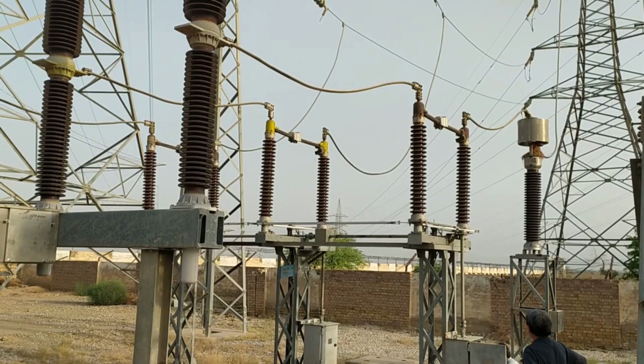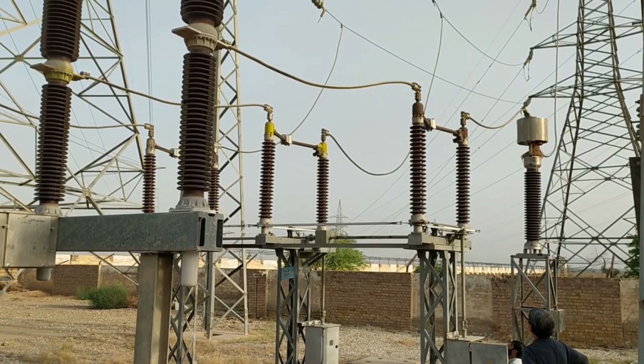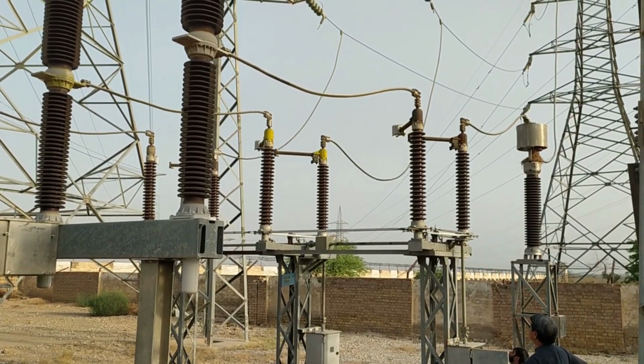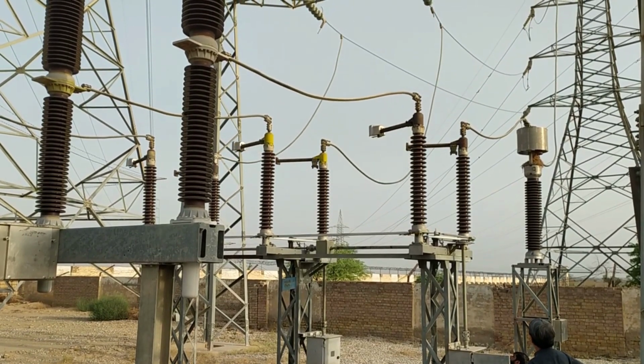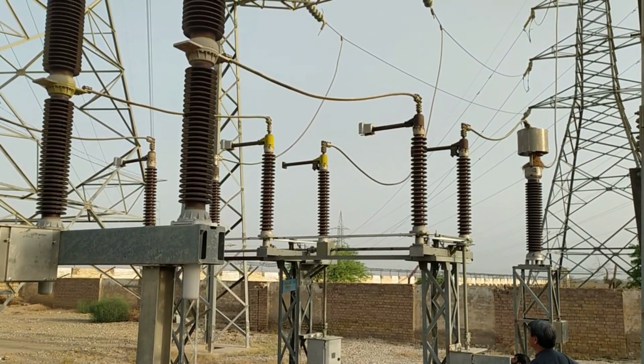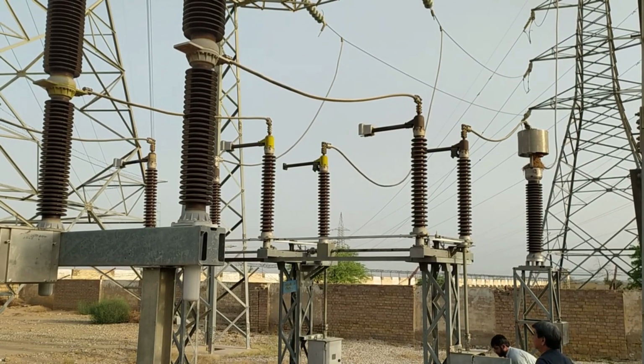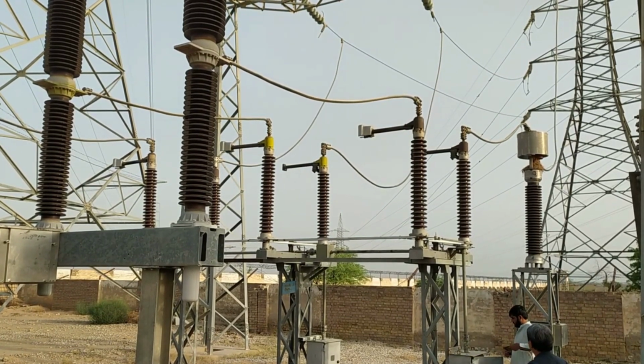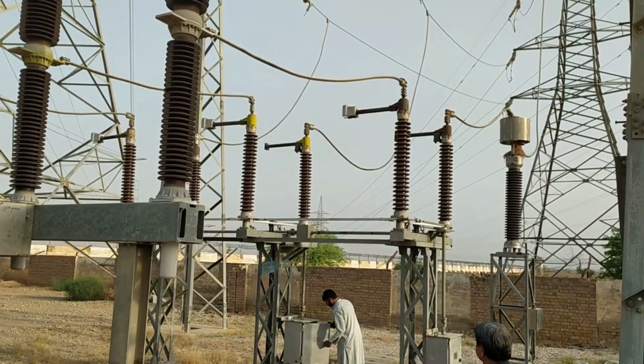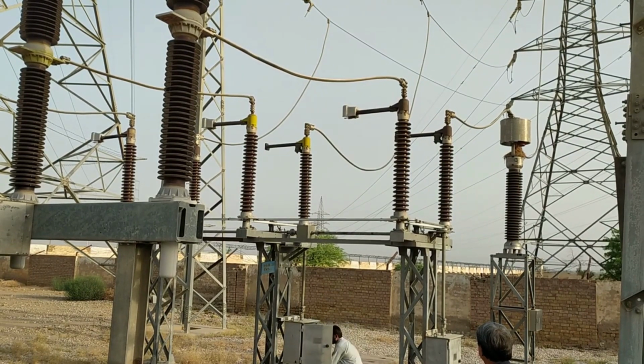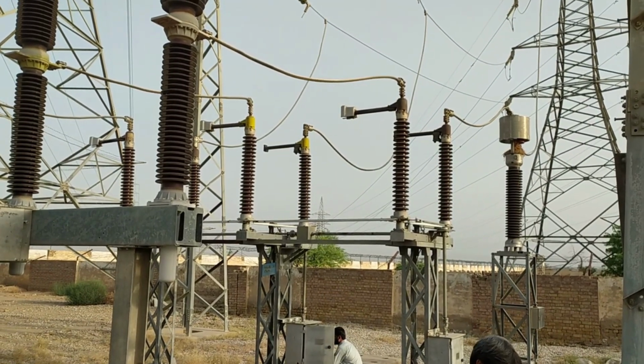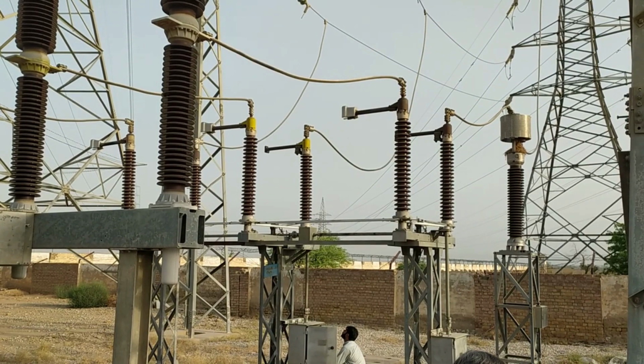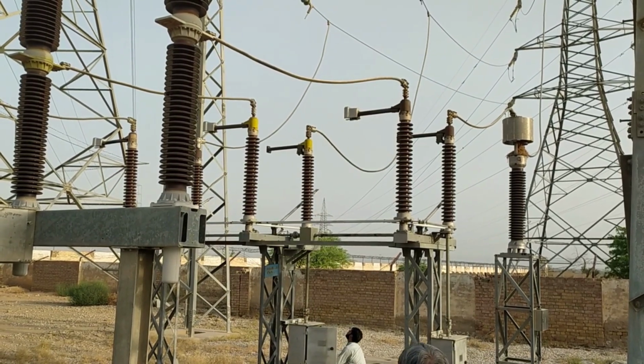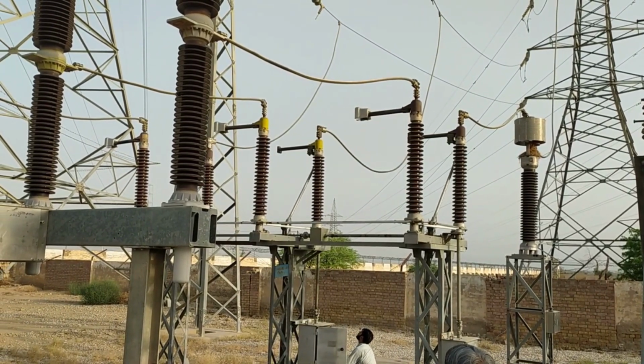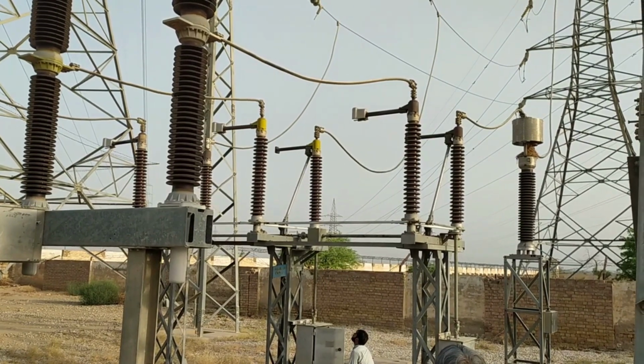On the flip side, isolators are the unsung heroes, quietly working behind the scenes. They are designed for manual isolation of equipment for maintenance, without the ability to interrupt current flow. Their interrupting capacity is lower, reflecting their role to isolate equipment during normal maintenance conditions, rather than in response to faults.